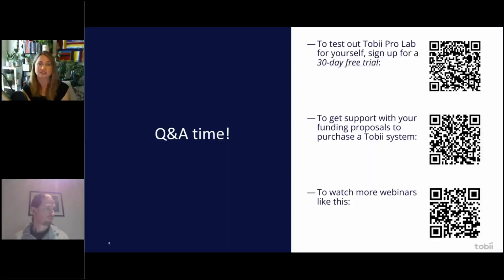Light level does matter, I think, to a certain extent, if the room is very dark versus being sort of natural light, right, Carol? So we recommend like 300 lux, that's the optimal, of course, but I assume that you don't really work in very extreme conditions. However, it will calibrate even in full darkness, because eye tracking is based on infrared light, and we have an illuminator that will illuminate the participant's eyes in any conditions. Yeah, the optimal is indeed standard room light.